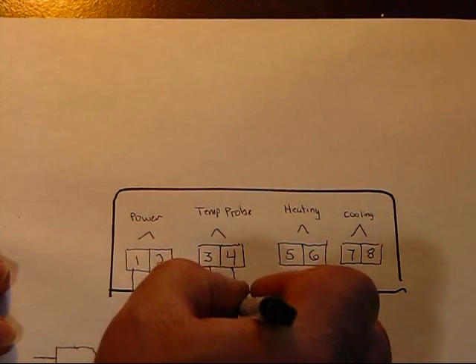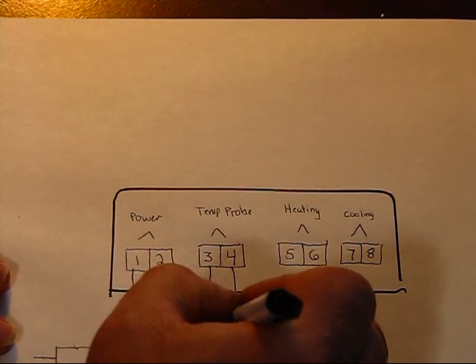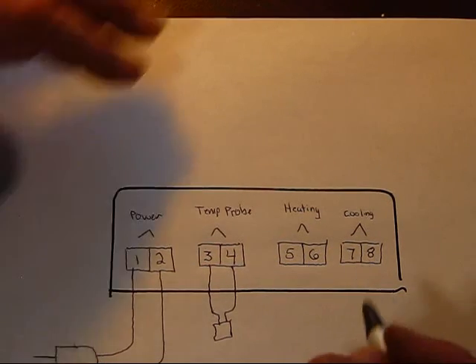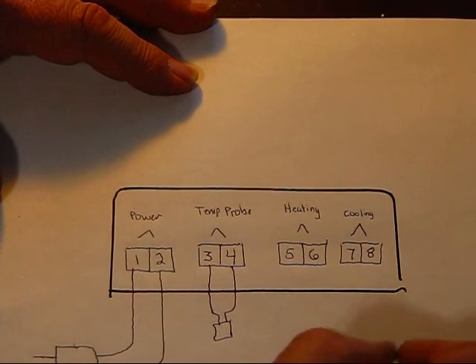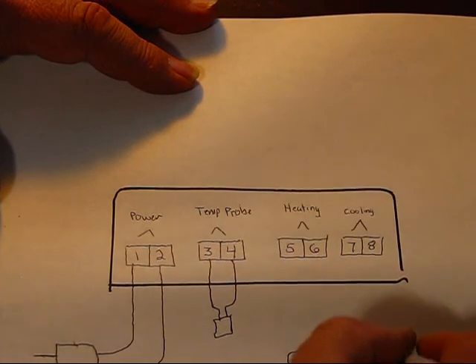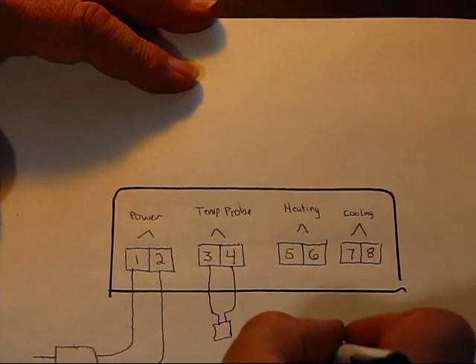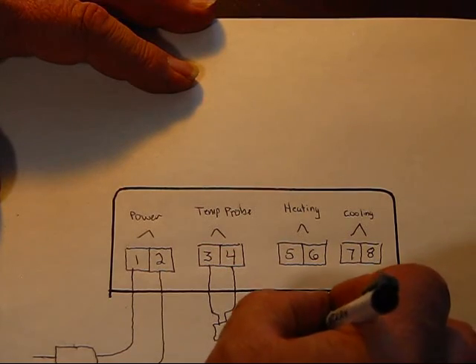Your temperature probe just comes out here. You got two wires on your little thermometer and it comes out right here. That's it. Just plug in your two temperature probes. Your heating element for your incubator.